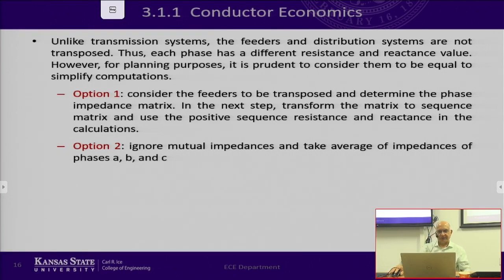There are two possible ways to simplify. One is to assume the feeder is transposed and determine the sequence matrix, then use the positive sequence values for calculating line impedance, assuming all three phases are identical. The second approach is to ignore the mutual impedance, take phases A, B, and C, and just use the average of the three for the calculation.